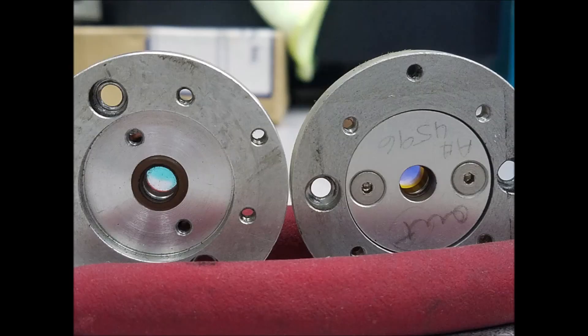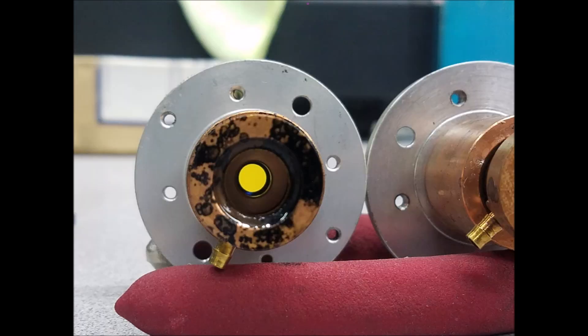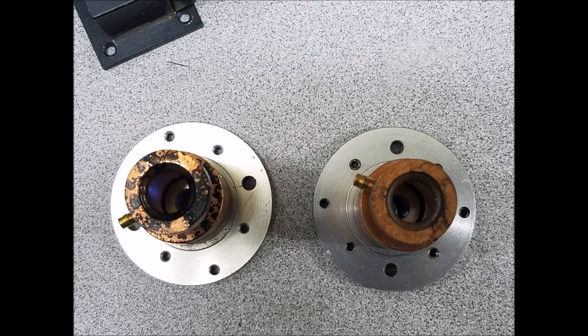Argon ion lasers have optical components on each end of the laser tube, the high reflector and output coupler. The output coupler is where the beam emits from, though it reflects most of the light back into the laser to maintain stimulated emission. The high reflector is on the back of the laser and reflects all the light that hits it. These two optics reflect light back and forth. Both of these optics were removed for cleaning. They also needed to be taken off before the laser tube could be taken out and cleaned.